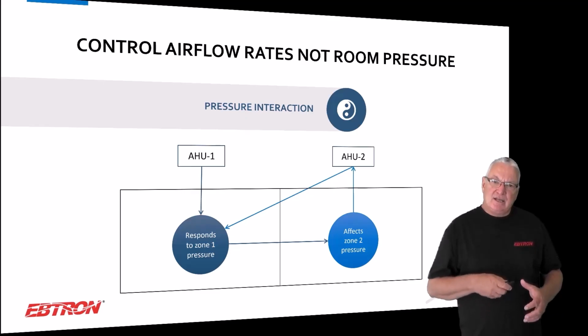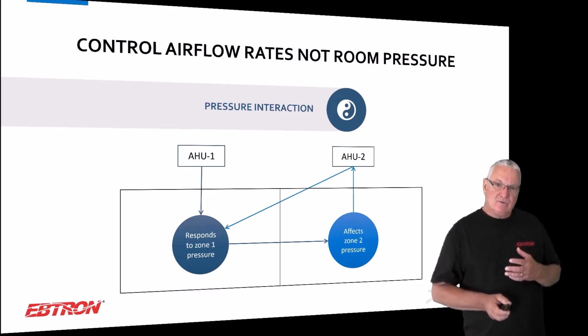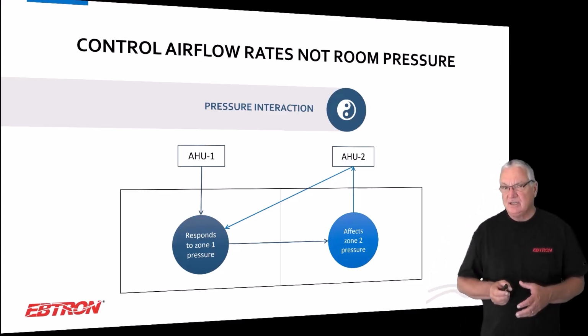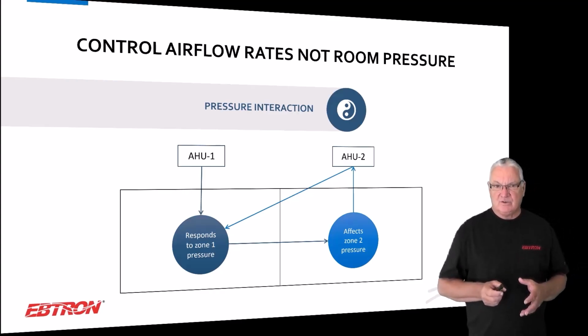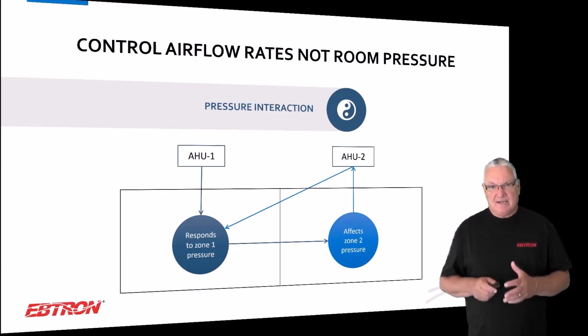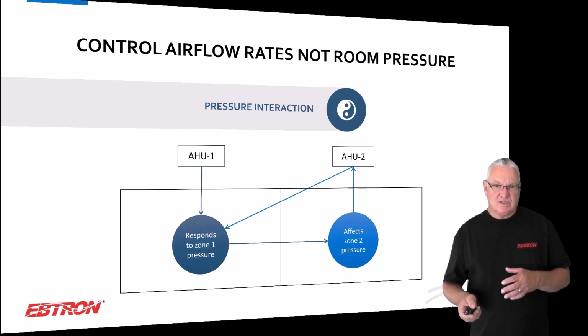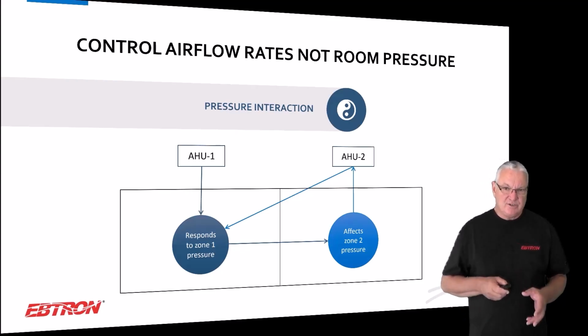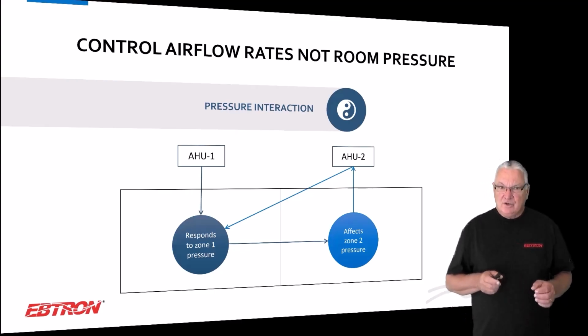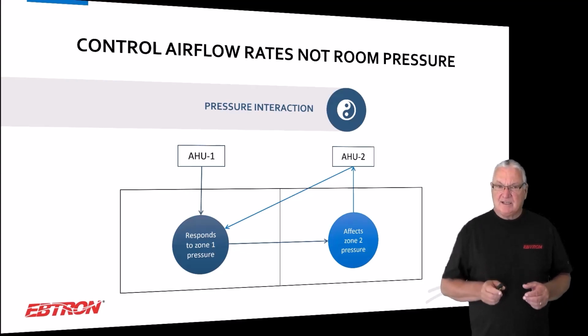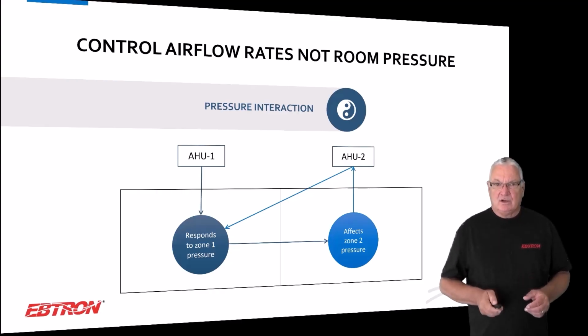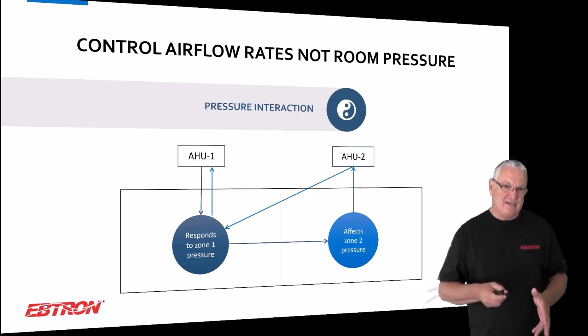And if it's a static condition where nothing's changing in all of these pressure zones, you probably can set it up and make it work. But if you have things that are changing within pressure zones, like exhaust rates changing in different pressure zones, then you're not really going to be able to isolate your pressurization and you're not going to get effective control, right? So that's one of the serious problems with it, okay? They just affect each other.